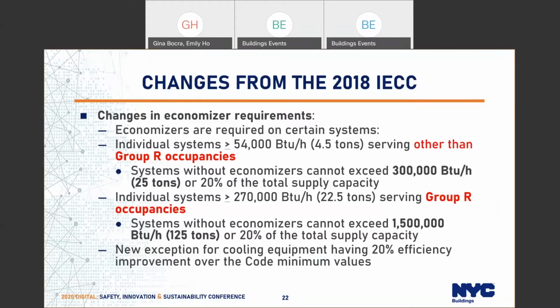This was probably the question or the code section that we got the most questions on for the 2016 code. And the way that code was written, it forced a lot of projects into using the ASHRAE compliance path because the economizer section was very stringent. So the state code, which adopted the 2018 IECC, relaxed those provisions for Group R occupancies. So, the economizer requirements are the same for other than Group R occupancies.